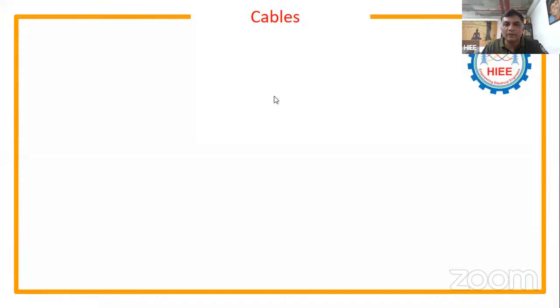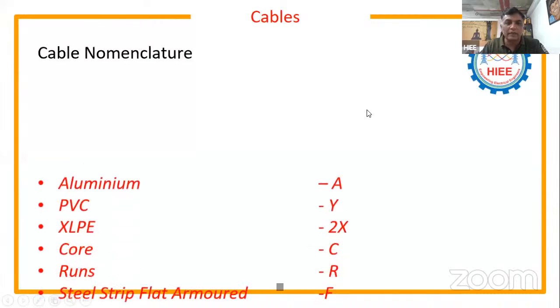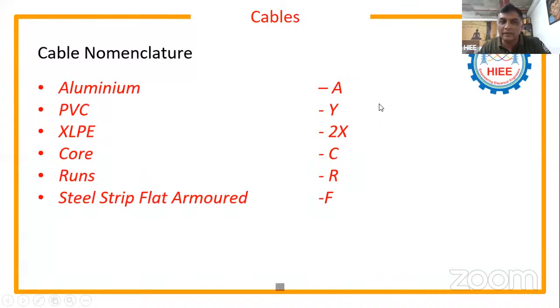So guys, so far we understood the classification of power cables based on the insulation, based on the conductors, and based on armoring. Now we need to understand the cable nomenclature. Generally, if you look at single line diagrams in an industrial application, somewhere people mention it like this: a single run of 3.5 core, 70 square mm, A2XFY cable. This is how people mention the cable.